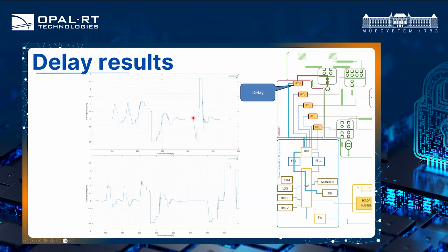Whenever there is a switch event, remember we have changed the set point, there is a step in the power balance which needed to be taken care of. Here you can see the control algorithm tries to create the same steps as the normal case, but everything takes longer. Although we've added just a few hundred milliseconds of delay, the actual response of the system has been pretty slowed down.